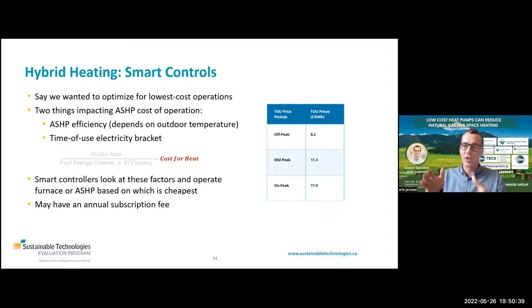You could imagine a smart, web-enabled controller that looks at all the real-time factors and makes a control decision: for this hour, operate the heat pump because it's cheaper, but for the next hour, go with the furnace because that's the cheaper option. This technology is available on the market today. Some of these systems have an annual subscription fee that can eat into the savings, so that's part of the discussion too. But the basic technological approach of this kind of smart switching is sound.